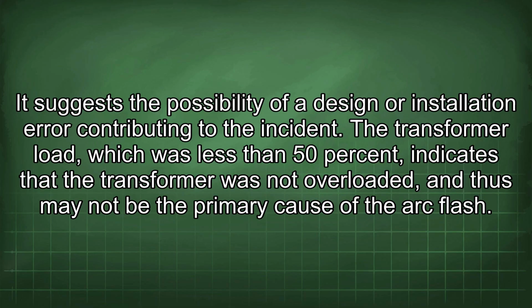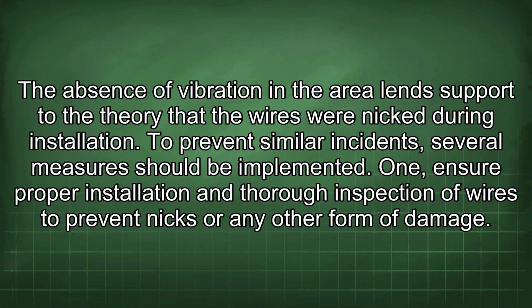The transformer load, which was less than 50%, indicates that the transformer was not overloaded and thus may not be the primary cause of the arc flash. The absence of vibration in the area lends support to the theory that the wires were nicked during installation. To prevent similar incidents, several measures should be implemented.